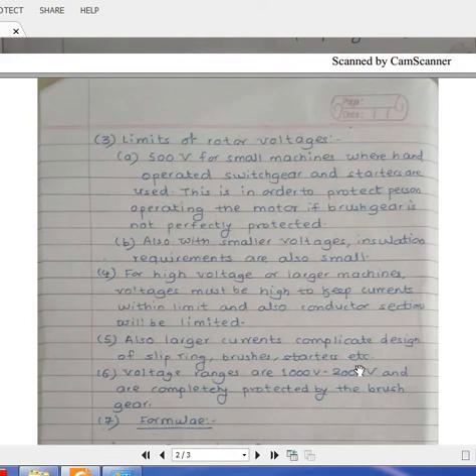Also conductor sections will be limited because you are going to reduce your current. Another benefit is when you are keeping your current under control, your design of slip rings or brushes or starter mechanisms becomes easy. Because for all these things your criteria for designing is always what is the starter current or the larger current.